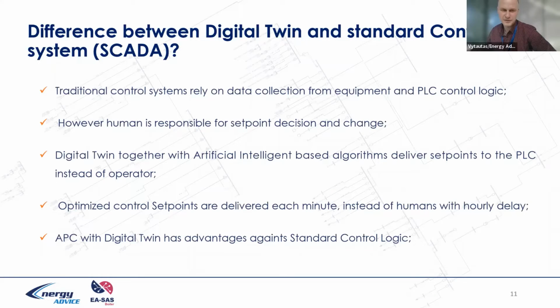First, the traditional control system relies on data collected from equipment. However, in general, a human is responsible for making set points and for adjusting them, or some adjustments are already integrated into the control system. But digital twin together with artificial intelligence algorithms delivers set points to the PLC instead of the operator, or adjusts these set points instead of the automation engineer who did this previously.